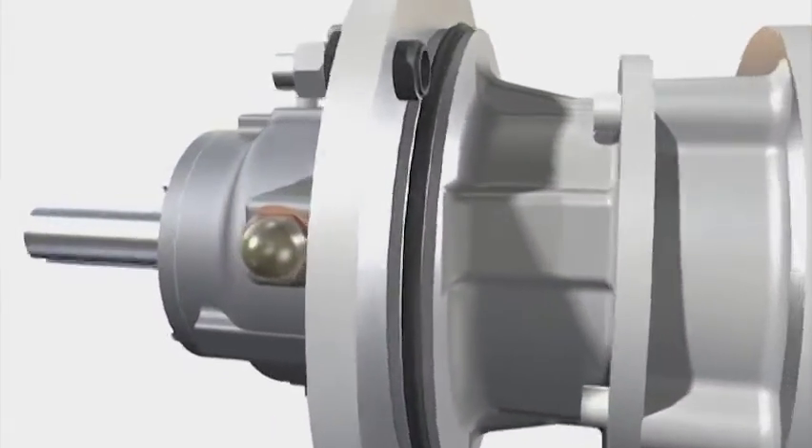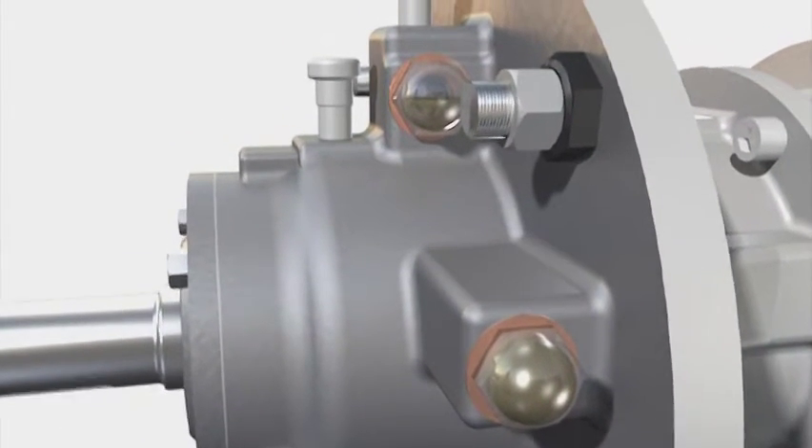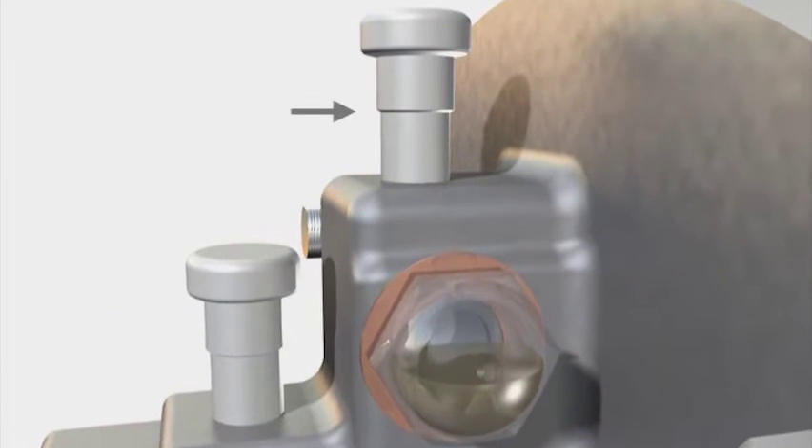Both high and low oil levels are monitored via the sight glasses, fitted high on the bearing housing, allowing the pump to be shut down when evidence of a seal failure is observed. A vent is also fitted at the top of the housing to maintain even atmospheric pressure in the oil chamber.